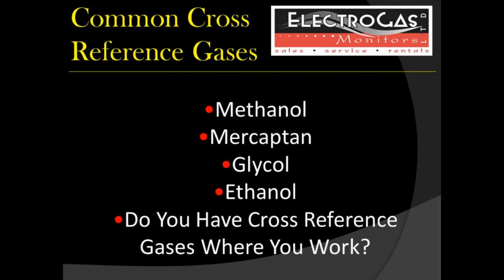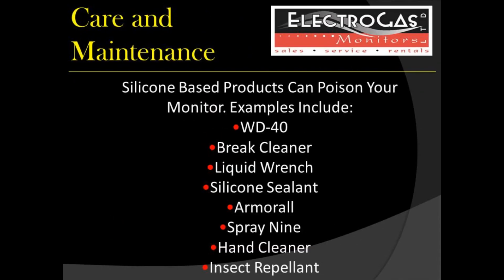In terms of performance, your monitor can be affected by cross-reference gases. A list of common cross-reference gases include methanol, mercaptan, glycol, and ethanol. Silicone-based products can poison your monitor during operation or even while turned off. Do not expose your monitor to any chemicals and clean it with only water. A list of common products that may cause poisoning is shown here.